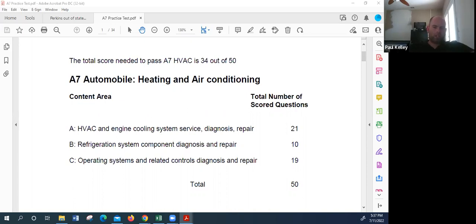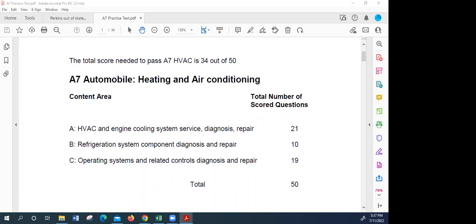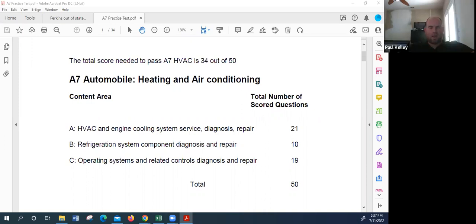What do you think that would cause on your gauges, high and low? Both low, right? More specific than that. Okay, so I'm gonna give you a little bit. If the compressor is sucking in and then kind of blowing by, almost back out the inlet valve, I agree the high side is not going to be that high. But the low side wouldn't be as low because it's not drawing the low side down. It's drawing the low side down and then kicking it back out, which is putting it back up.